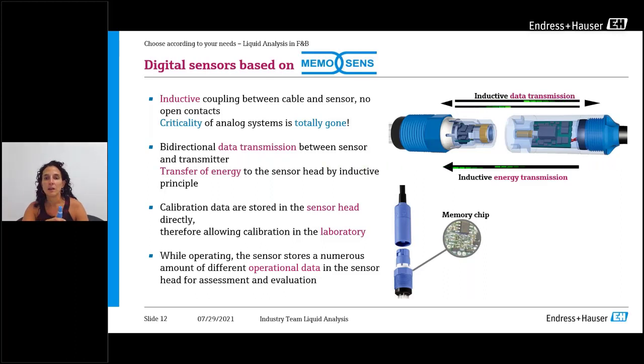So I could see when it was calibrated, the last 8 times, the last 8 results. I can see, okay, last time I calibrated 3 weeks ago, so perhaps I should do the calibration again. Also, I have how many hours it was working, when it was installed, how many hours it was working even in higher temperatures as it should. And that gives us a lot of flexibility.